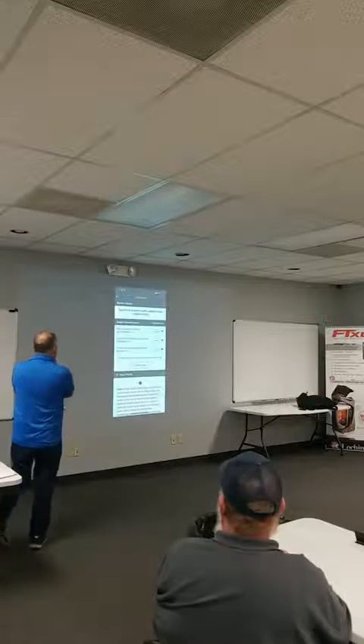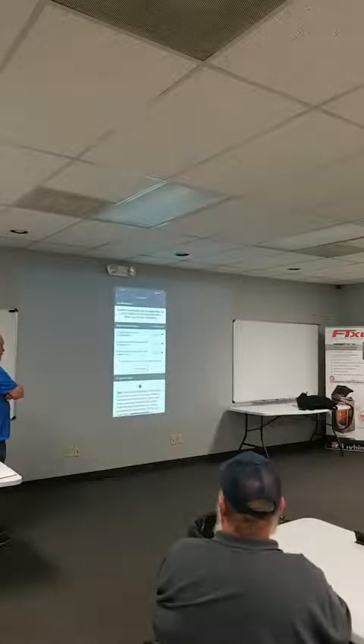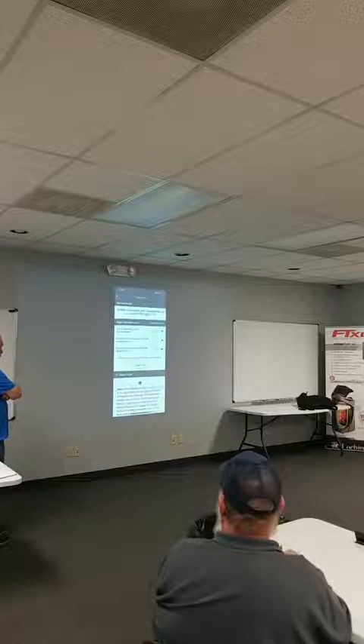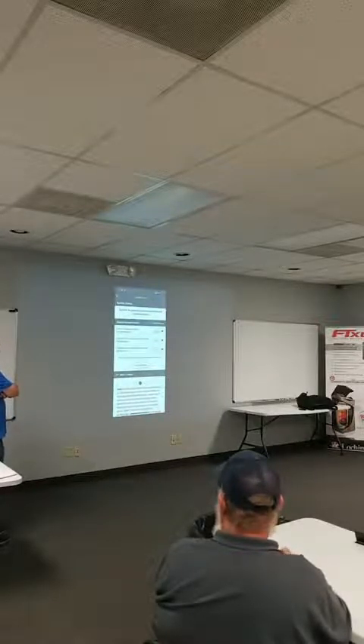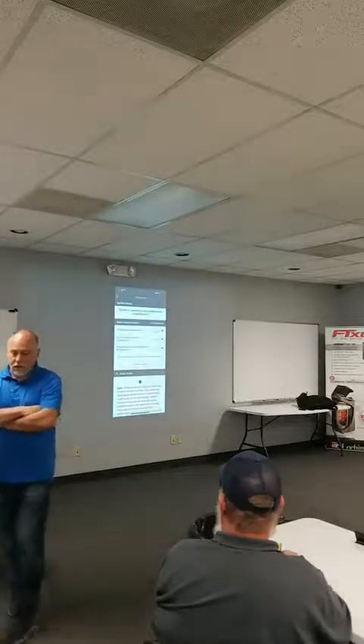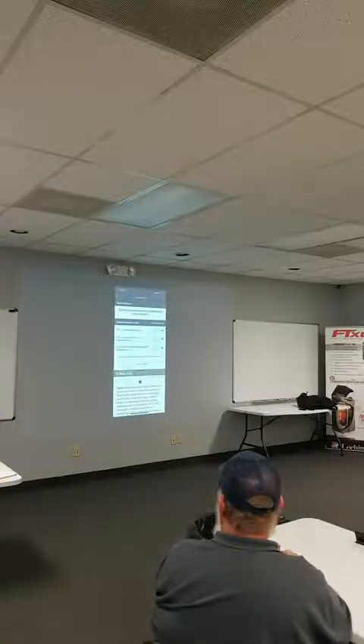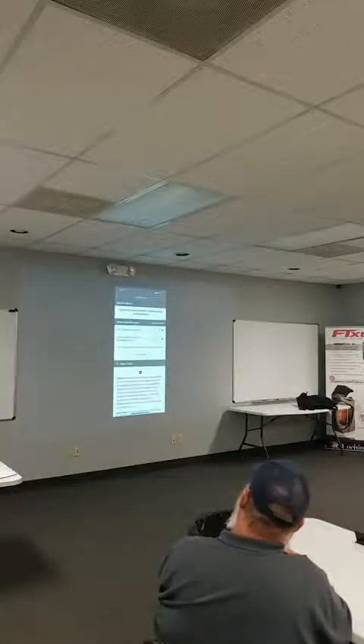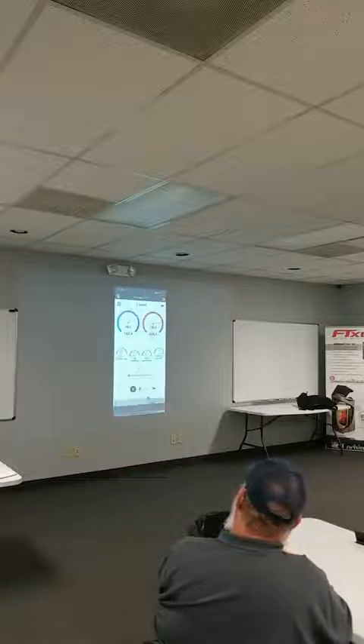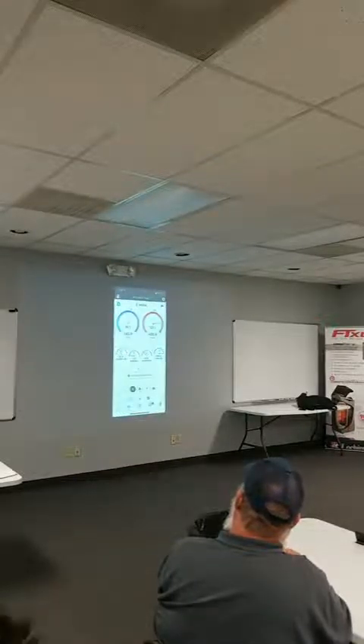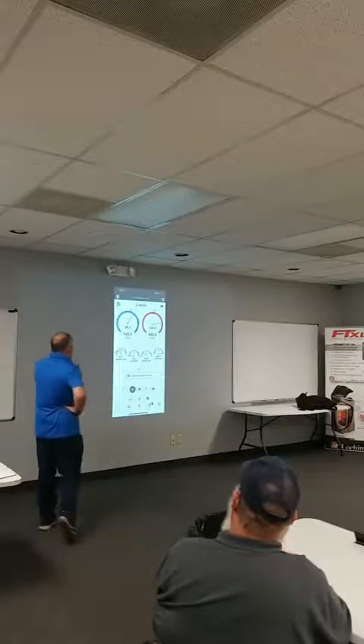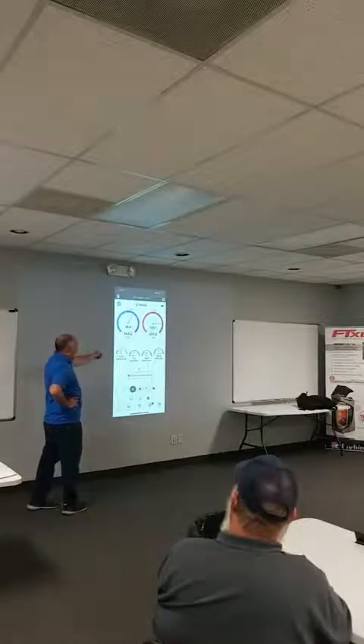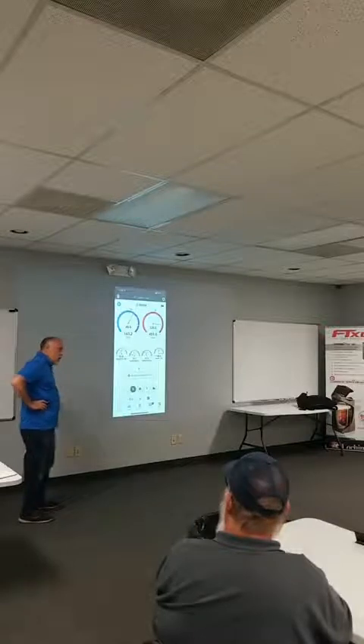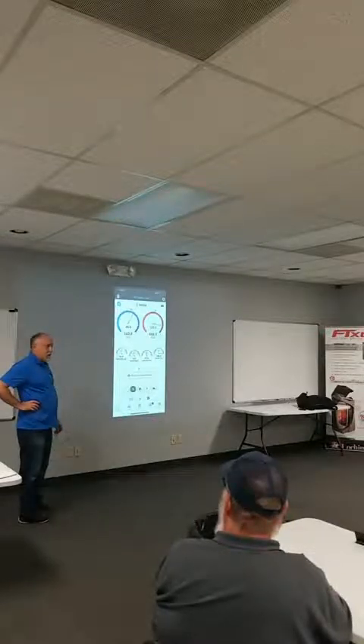So as soon as he plugs that condenser fan up, now we're getting 4 symptoms of a dirty condenser, and it could be an overcharge. Right now we know it already is overcharged, but it's picking up the dirty condenser. It's going to bounce around a little bit until it's stable, so you might get some different flags in there. Now, why is it saying the TXV bulb may be loose? Well, what happened as soon as he blocked the condenser off? Oh, superheat. We forced the head pressure way up. The TXV couldn't respond fast enough, so it just jammed the liquid to the TXV and dropped the superheat in the toilet.